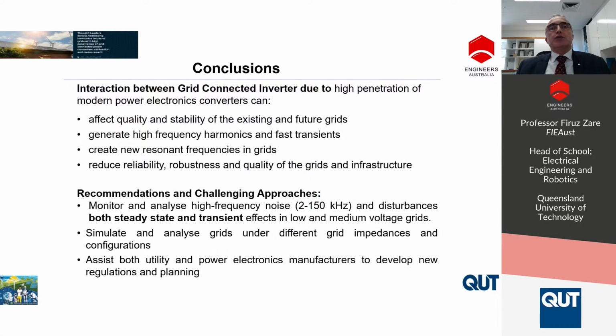So I'm going to finalize my presentation and give the conclusions in terms of high-frequency harmonics in the network. Based on reports, analysis, measurement, and the working group in standardization, high-frequency harmonics can affect the quality and stability of the grid because of tripping and failures. Harmonics in the network, especially high frequency, are not steady state for hours. They can be severe transients or short-term events within a second or a minute that we need to measure. Because of power electronic filtering systems, we have resonances in the network, which is different from old technology. Those can affect the reliability, robustness, and quality of the grid and infrastructure, especially cables and transformers.